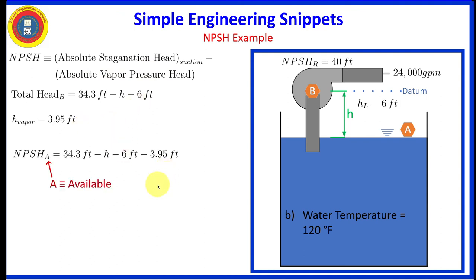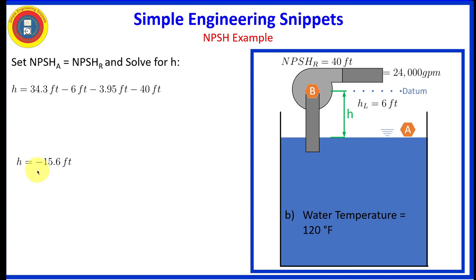We need to subtract from that the vapor pressure head. And when we do that, we set that equal to the required net positive suction head, which again is still 40 feet, and solve for H. And once again, we get H is equal to a negative, this time 15.6 feet. Again, the negative sign indicates that the pump location must be 15.6 feet below the surface of the water.